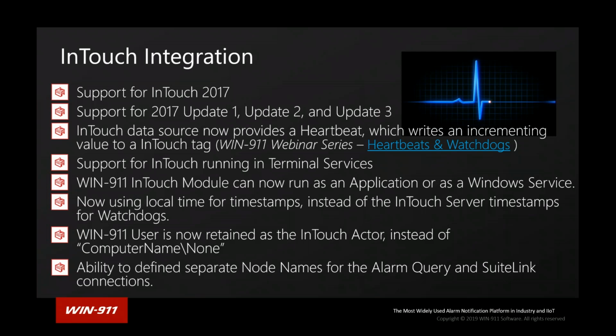We had run into some issues after the initial releases of our InTouch module to InTouch systems running in terminal services. This had to do with the way WIN-911 interacts with WindowViewer, and how we could only connect to a WindowViewer running in the console session. When running in terminal services, multiple instances of WindowViewer are launched, and we need to make sure we're connecting to the right one, particularly the one that has the alarm manager running on it.